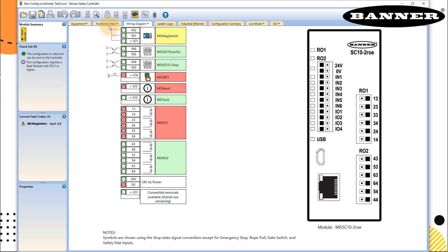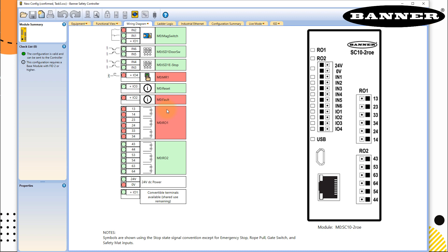And using the software, you can also program if there is any such fault, you can have a different LED color on your reset switch. So now you know immediately that you program this for any fault in the input, you will go check all the sensors, everything is okay. If not, just go there, realign your sensors. And now everything looks back, looks great. And the color changes to blue, super easy, go there and reset. And now all the outputs are true again.